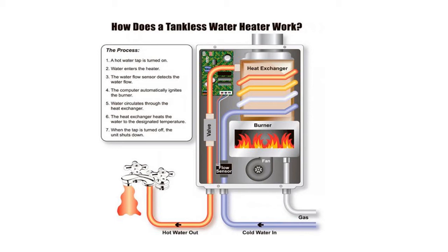However, a tankless water heater's output is limited by the flow rate. Typically, a tankless water heater provides hot water at a rate of 2 to 5 gallons per minute. Gas-fired tankless hot water heaters produce higher flow rates than electric ones.